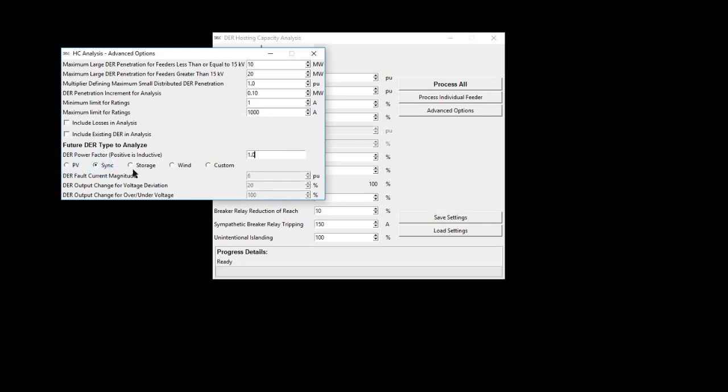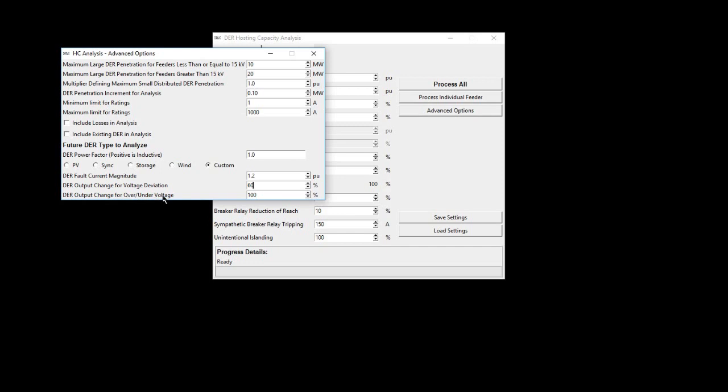By choosing custom characteristics, the user can manually define the DER fault current magnitude and the DER output variability. There are two characteristics for output variability to distinguish the difference between short-term voltage deviation and potentially longer-term over-voltage and under-voltage impacts.